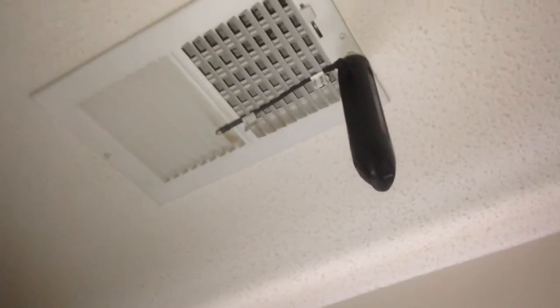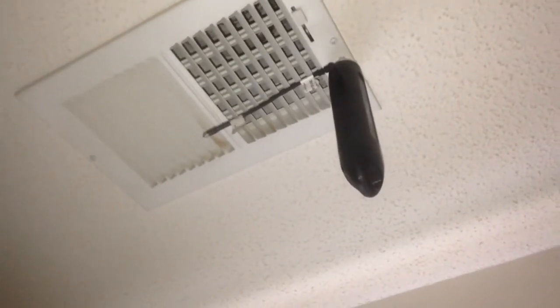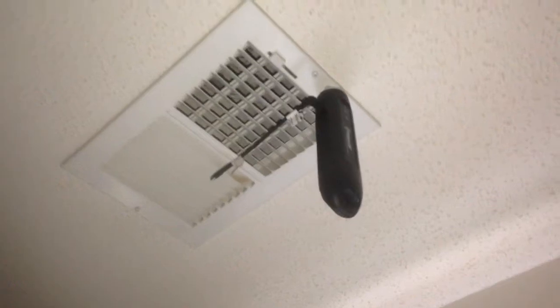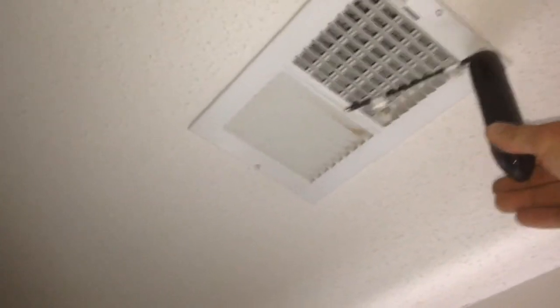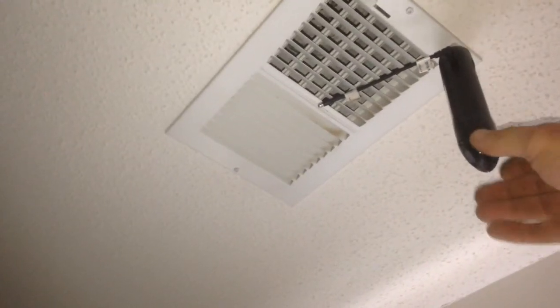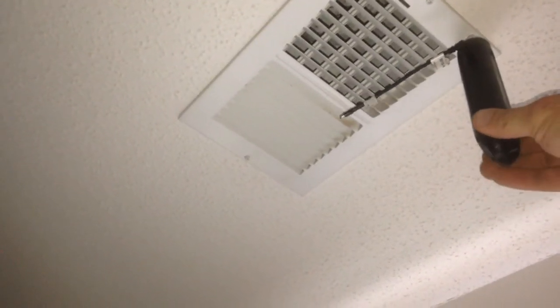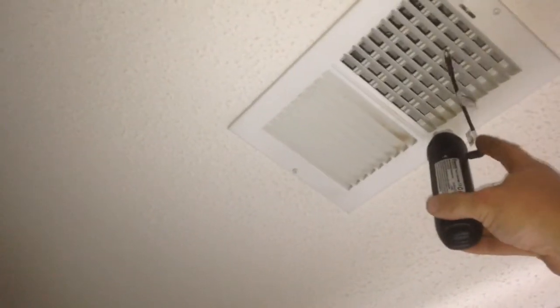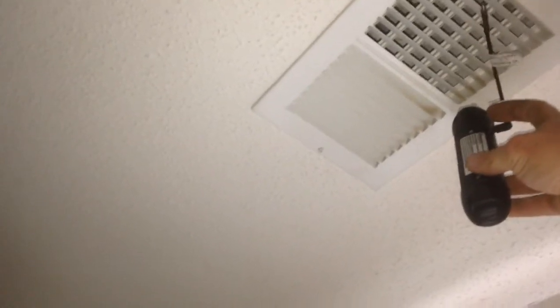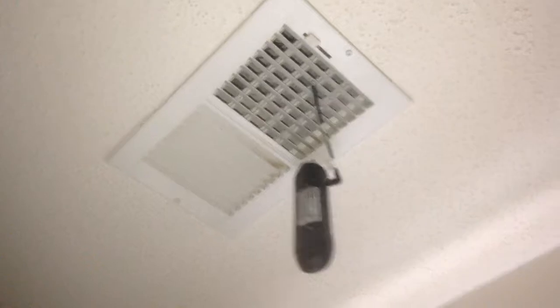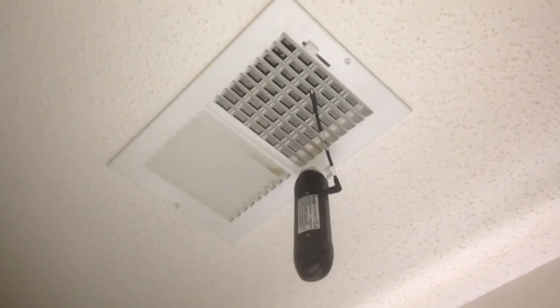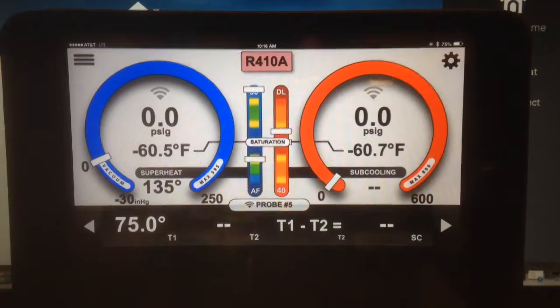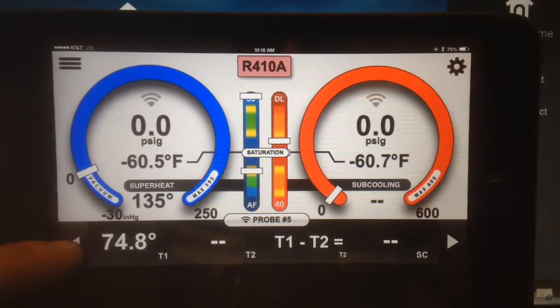And then we've got that ambient air sensor plugged into the T1 port, and it ought to get some air coming off of the register. Trying to get it to where it makes sense in the airstream. Let's do it this way. Since these louvers deflect air, that direction will get it so that probe hangs out in front of that set of louvers on the register. So we've got our repeater probe showing ambient around that register.